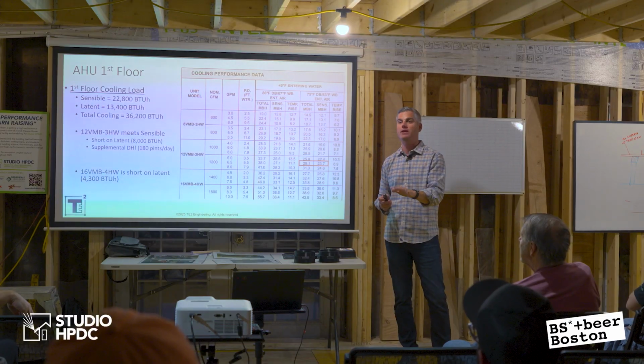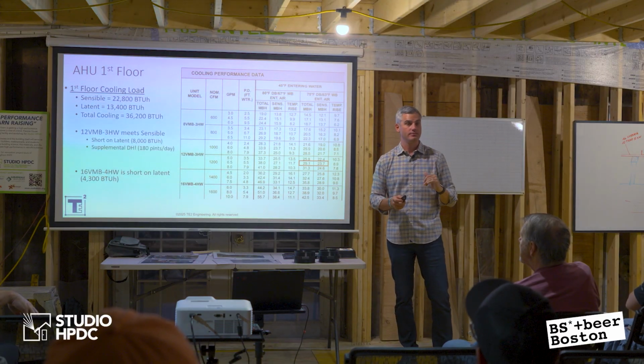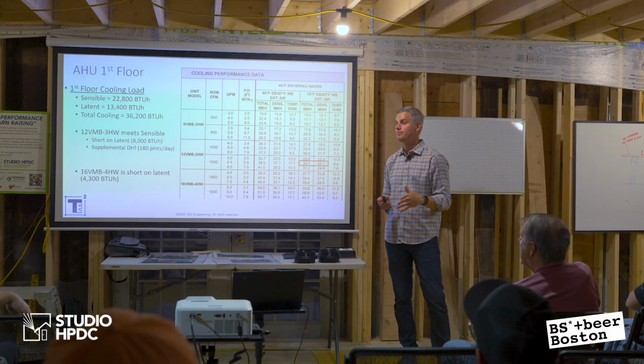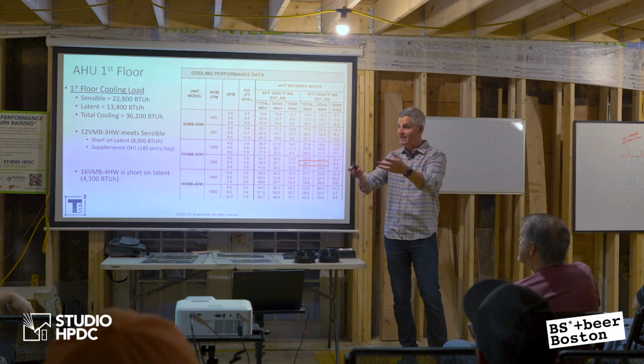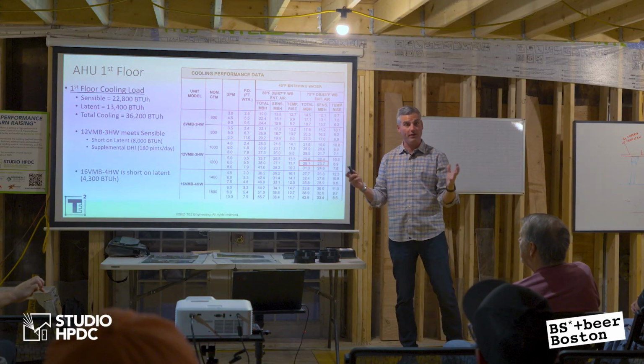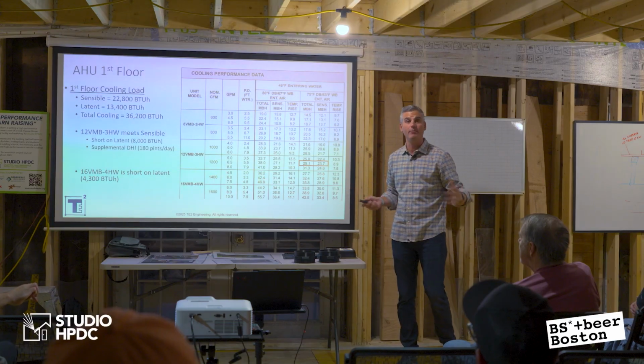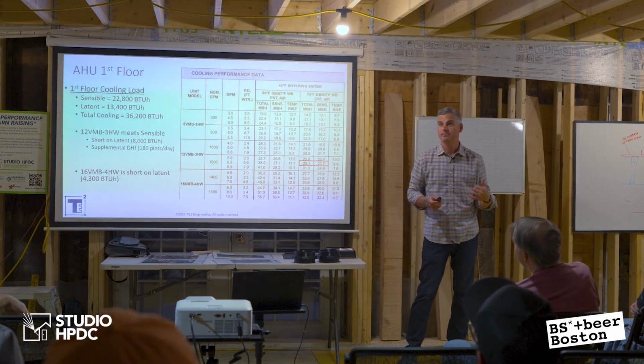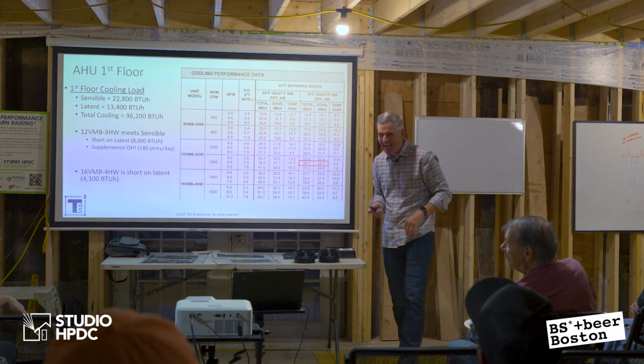If you have 55 people in here, the humidity is going to rise. The cooling system will not be able to keep up. If the client doesn't care about the relative humidity rising for that short period of time, then maybe we can get away without it. But in reality, we should have it.